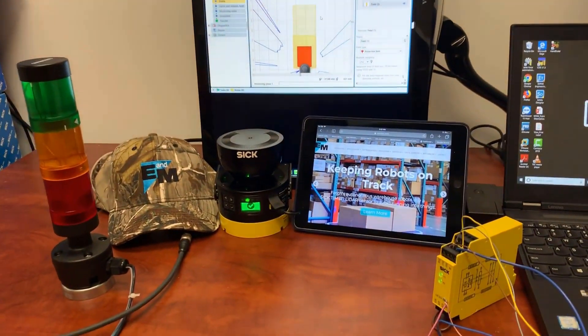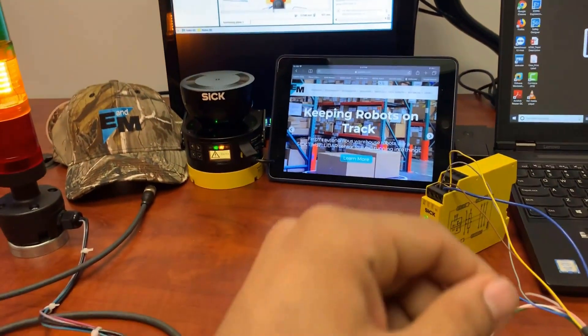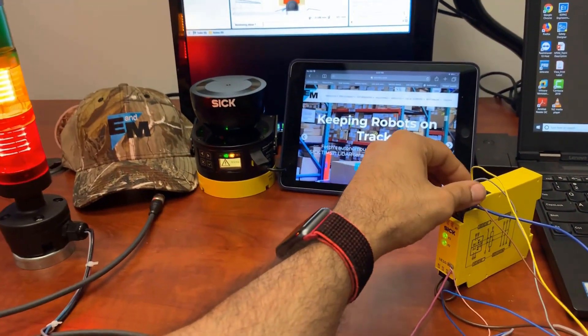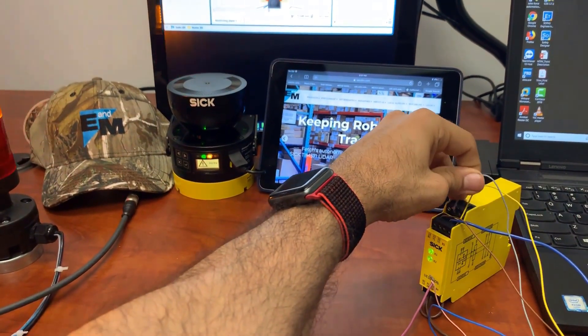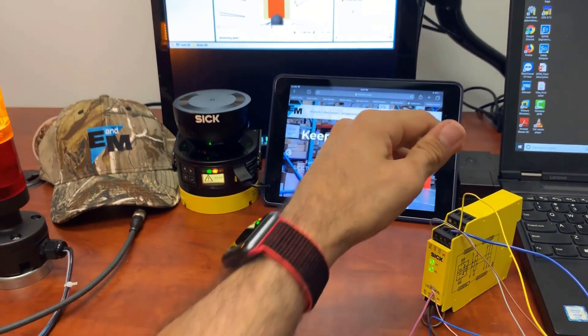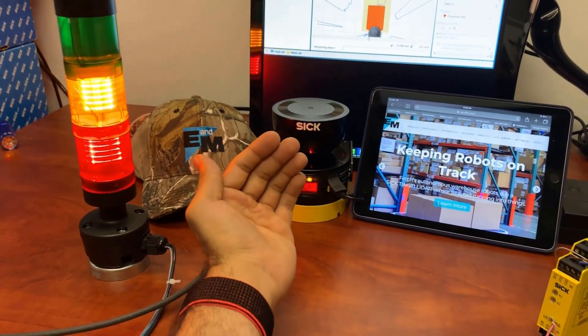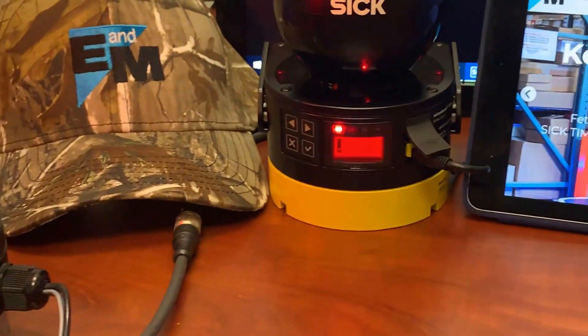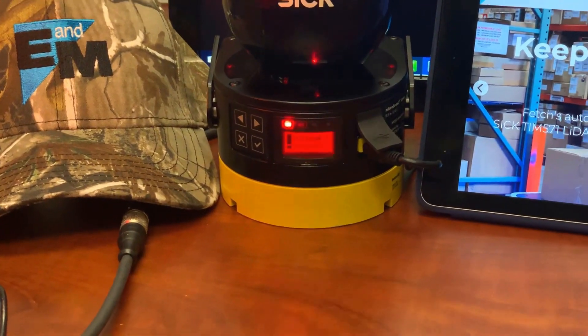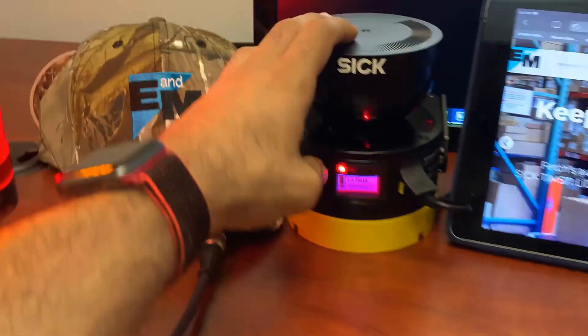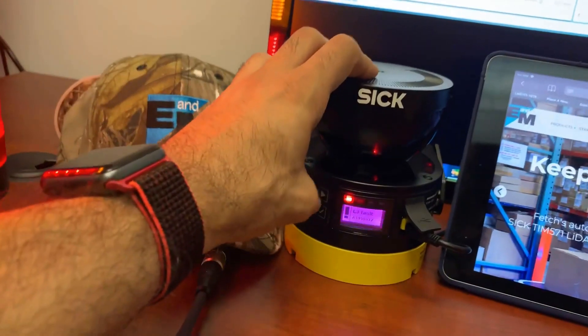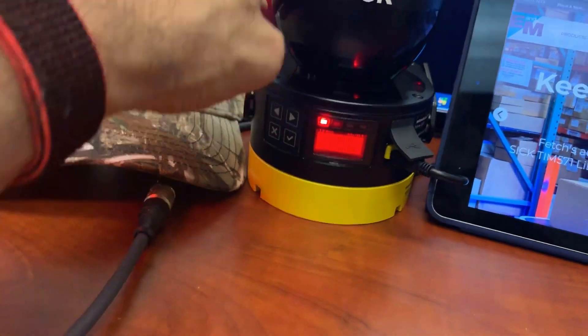Let's check the EDM. So EDM, we had it with the Y1. Let's break the circuit and as soon as I take it out and you breach it once, here it goes. You can very clearly see it's giving L3 fault and what is L3? It says that fault in external device monitoring.